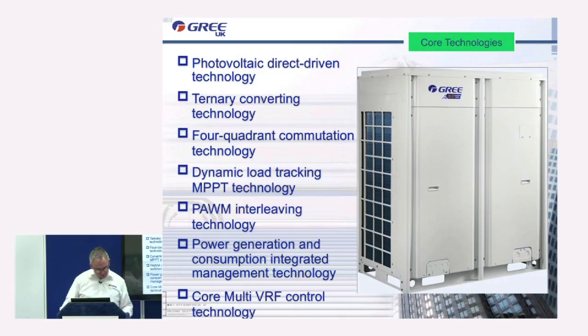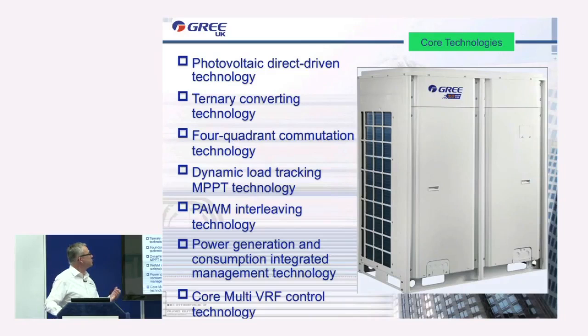So I'd like to just talk a little bit about the 7 main core technologies involved in this particular unit. First of all, the PV direct driven technology. The important point about that phrase is that it is direct. So basically it means we can connect directly from our solar array to the unit. There is a plus and a minus connection on the unit. So if you've got an array of panels and you have a combining unit, you literally just wire to the unit itself, and it's directly driven. We also have ternary converting technology. So this is the three main elements that we convert to use for our power flow. We have 4-quadrant commutation technology. Again, I'll explain this in a moment. This is to do with the harmonics. This is to do with the control of power flow in a good way.